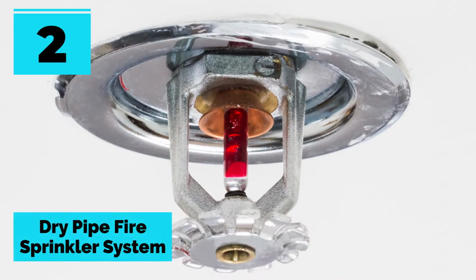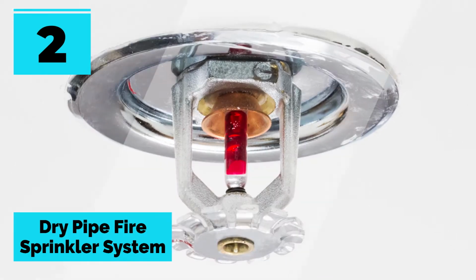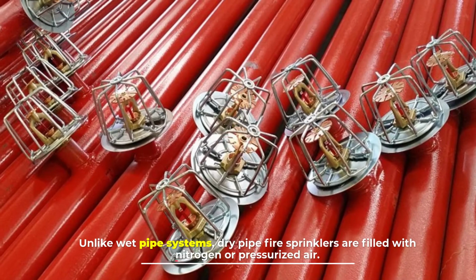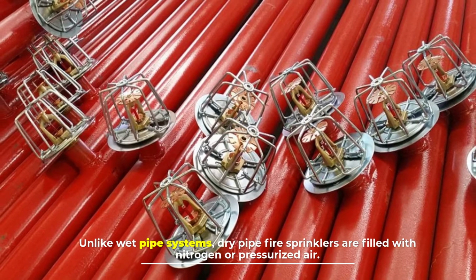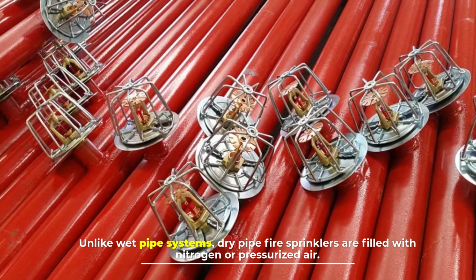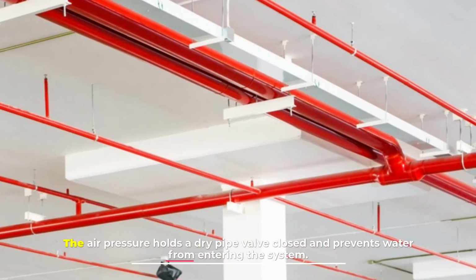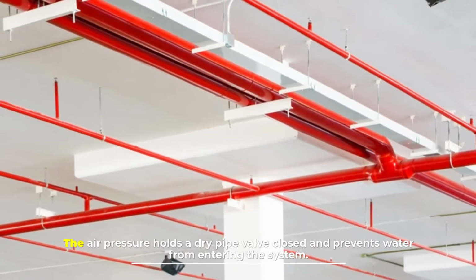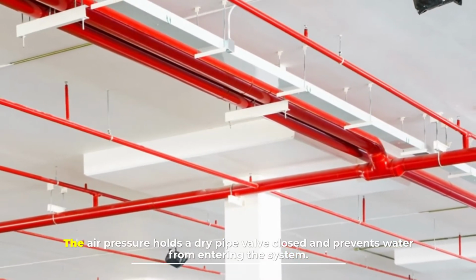Number 2. Dry pipe fire sprinkler system. Unlike wet pipe systems, dry pipe fire sprinklers are filled with nitrogen or pressurized air. The air pressure holds a dry pipe valve closed and prevents water from entering the system.